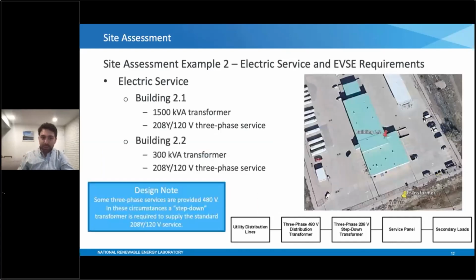However, we'll take a look at building 2 real quick first to see if that's a better candidate. And they actually had a much smaller transformer there too. It's a smaller building in general, and a 300 kVA transformer rating there also supplies this 480 volt service that the facility must then step down with a transformer to operate at their 208 volt service. And here we go, as I mentioned before, some 3-phase services are provided a 480 volt service. In these circumstances, a step-down transformer is required to supply the standard service. And we have a similar line diagram here where the utility distribution lines service that 480 volt distribution transformer, which must then be stepped down again by a facility transformer to 208 volts, at which point you have the service panel and secondary loads.